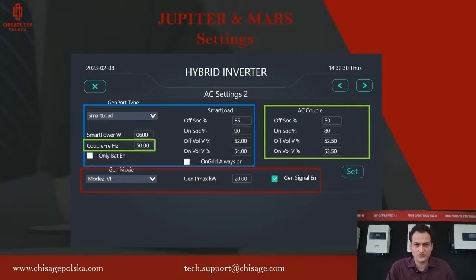For the smart load, we fill in all the blue frame. So we have to fill in the battery state of charge on and off when we want to use this smart load. We have to fill in the smart power in watts. That smart power means the minimum power from PV panels we want in order to start the smart load. So now it's 600. So if the PV panels give minimum 600 watts, the smart load will start. The state of charge for the battery is 90 and 85, so it will work between these two values.